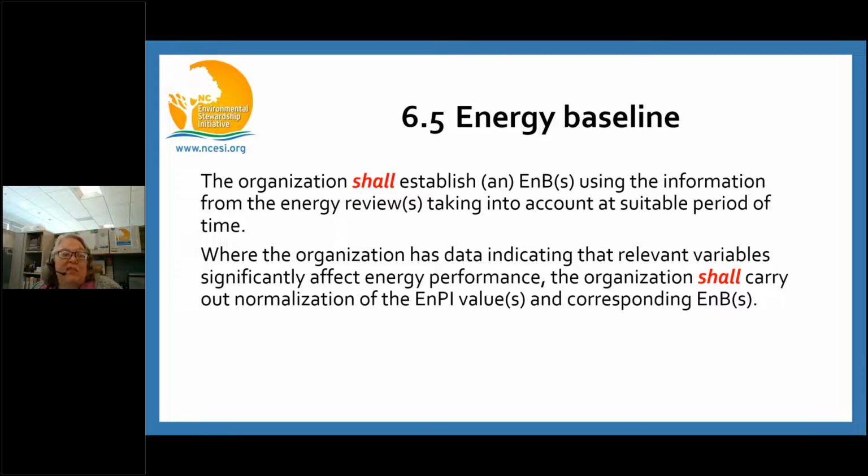So the standard says the organization shall establish an energy baseline using the information from the energy review, taking into account suitable periods of time. Where the organization has data indicating that relevant variables significantly affect your energy performance, the organization shall carry out normalization of the performance indicator values and corresponding baselines. So normalization for energy usage that's affected by something specific. The standard requires normalization to that variable.